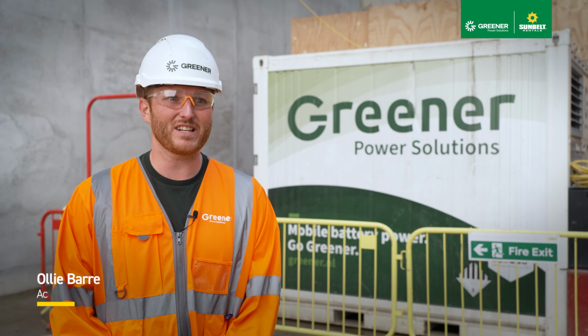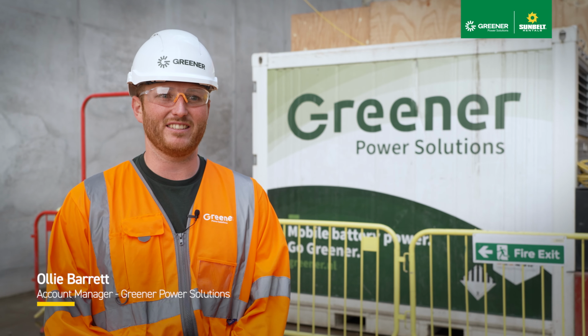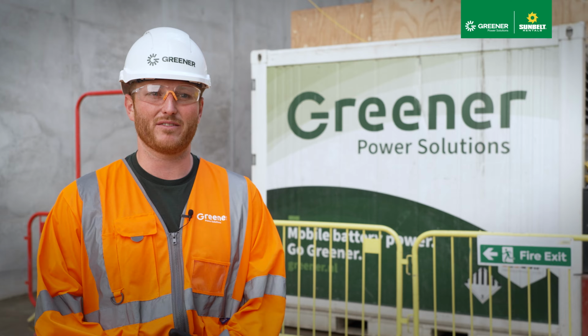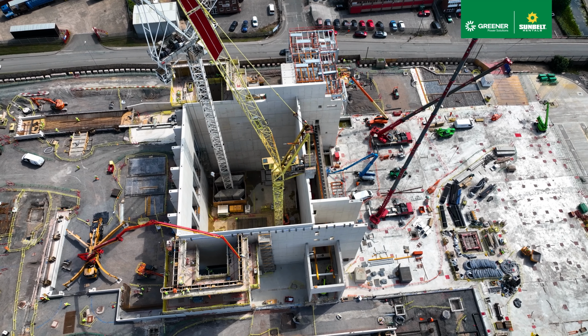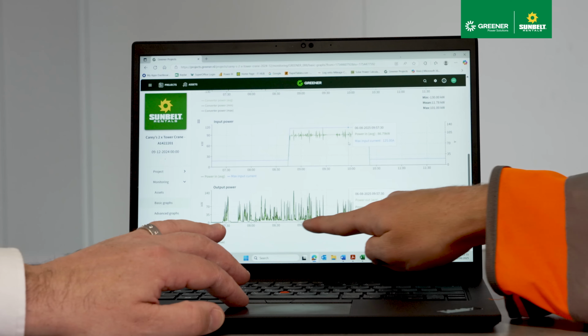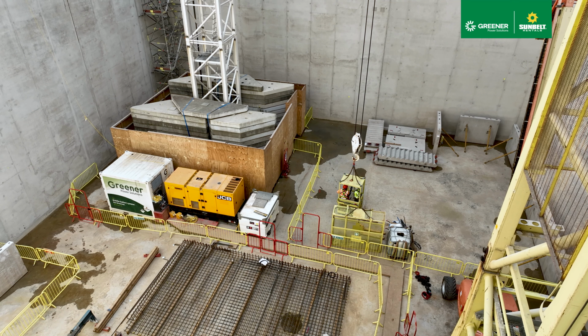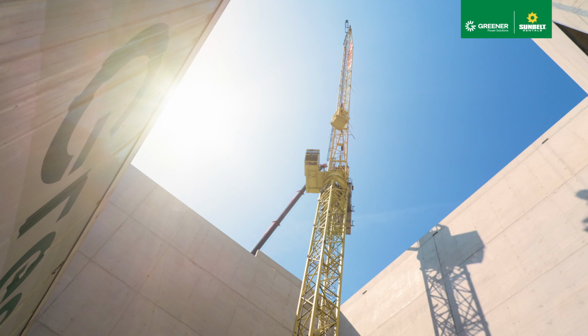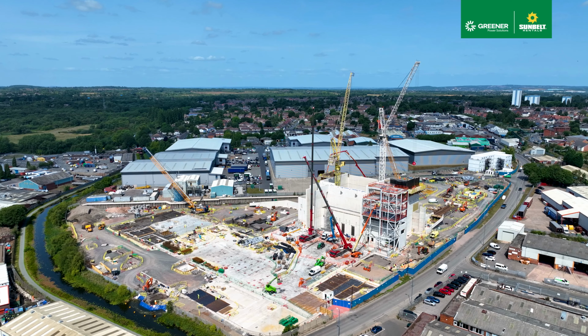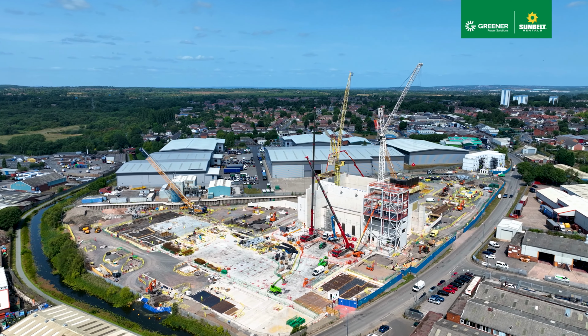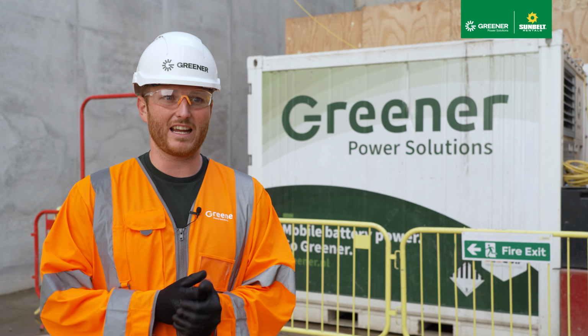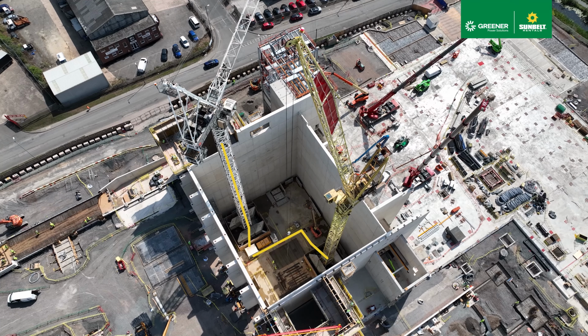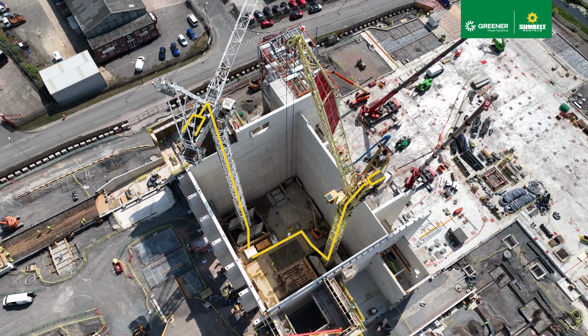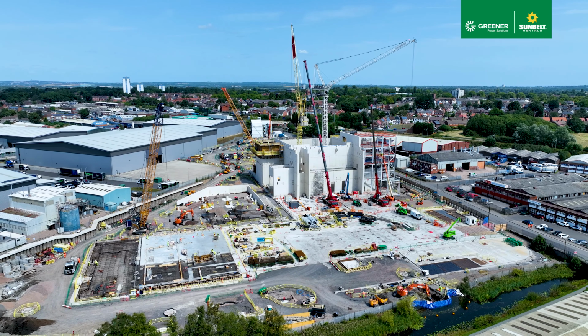Greener has supported this project by working with Sunbelt Energy Solutions to look at the spec of the tower cranes. Each of these tower cranes had a 400 amp inrush current. We looked at that and determined that using our battery alongside the 300 kVA generator would be enough to support the maximum load requested, but we could do it in a more sustainable way, with the battery delivering the load most of the time and only calling on the generator for charge cycles.